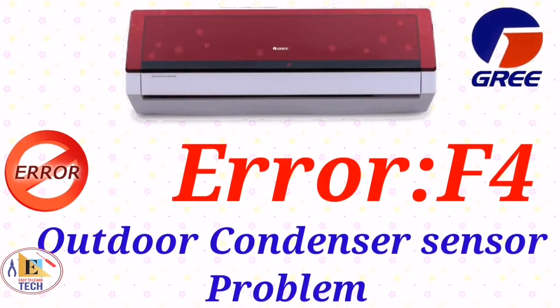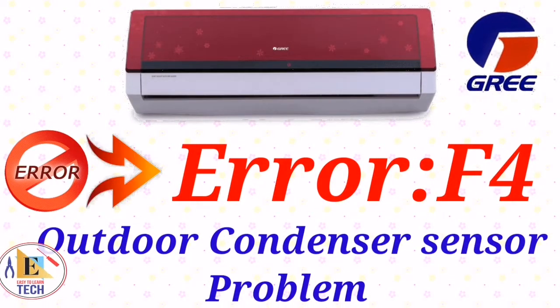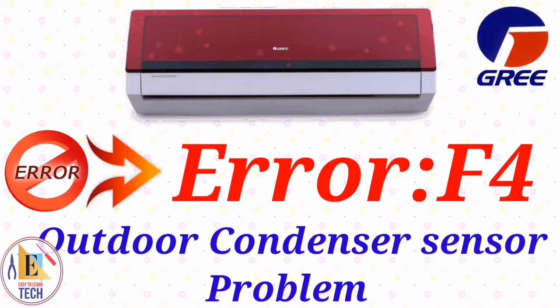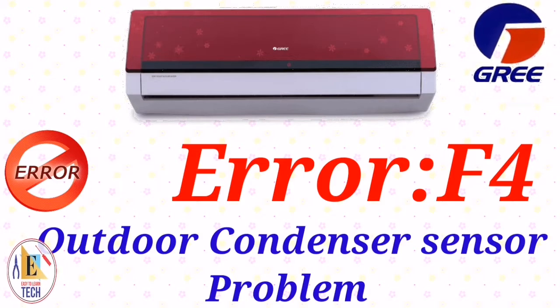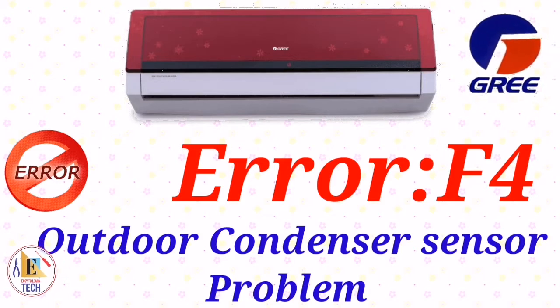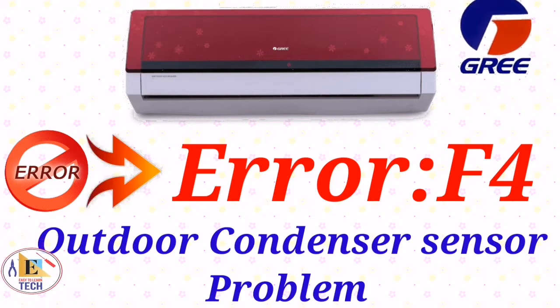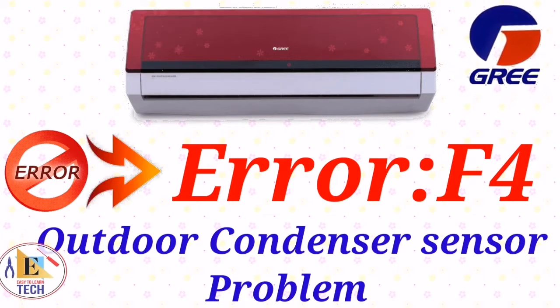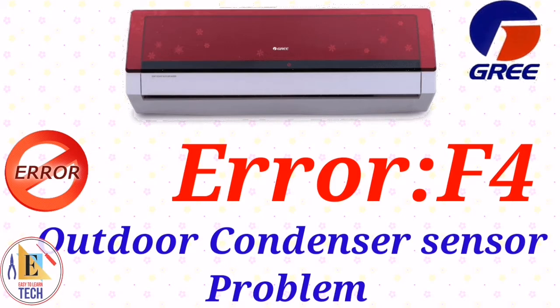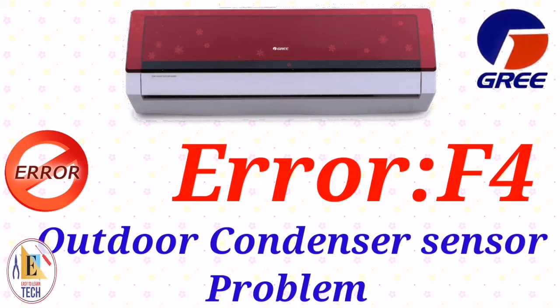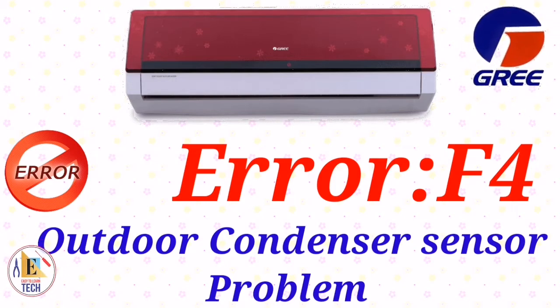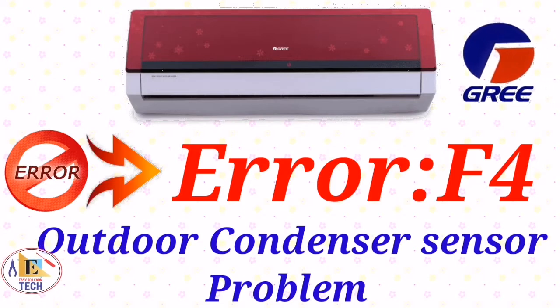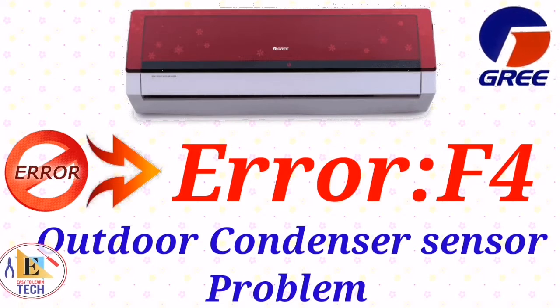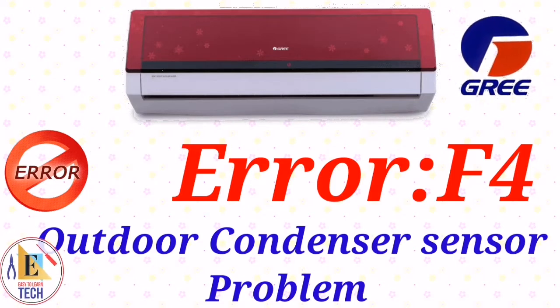When you see the error F4, it means outdoor condenser sensor problem. It is also called the outdoor ambient sensor. First of all, you have to check the placement. Then you have to check the wire between the sensor and our PCB. Then you have to check the connection of our PCB, if it is properly connected in our PCB or not. If it is properly connected, then you have to check the resistance. If the resistance is okay, it means our sensor is okay. If the resistance is not good, then you have to change the sensor.